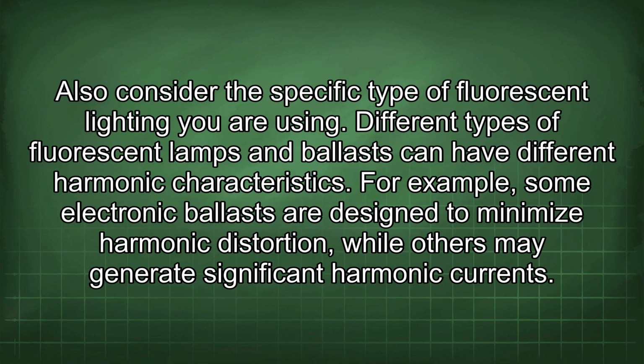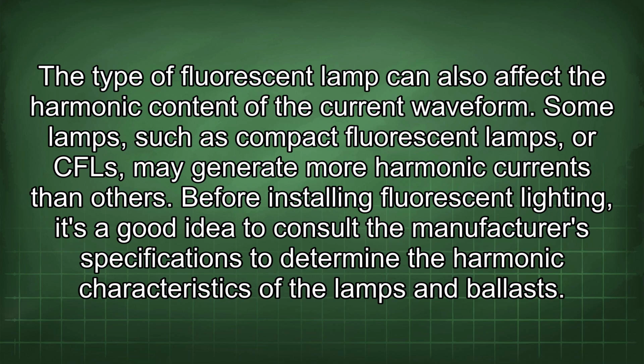Also consider the specific type of fluorescent lighting you are using. Different types of fluorescent lamps and ballasts can have different harmonic characteristics. For example, some electronic ballasts are designed to minimize harmonic distortion, while others may generate significant harmonic currents. The type of fluorescent lamp can also affect the harmonic content of a current waveform. Some lamps, such as compact fluorescent lamps, or CFLs, may generate more harmonic currents than others.